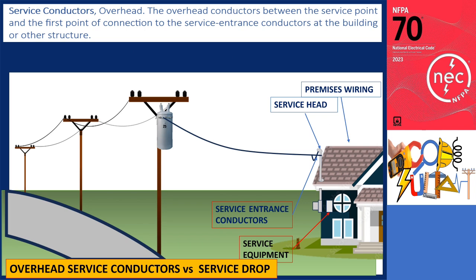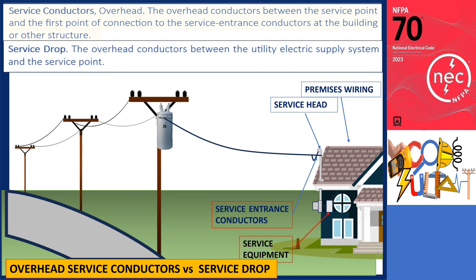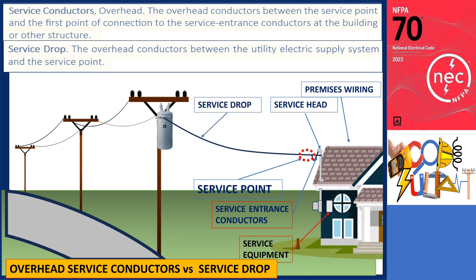Overhead service conductors refer to the conductors running between the service point and the initial connection point with the service entrance conductors at a building or structure. On the other hand, a service drop is defined as the overhead conductor that connects the utility electric supply system to the service point. In the provided illustration of an overhead installation, if the service point is located near the service entrance, these conductors are referred to as service drop.